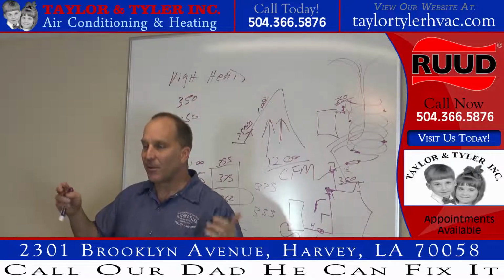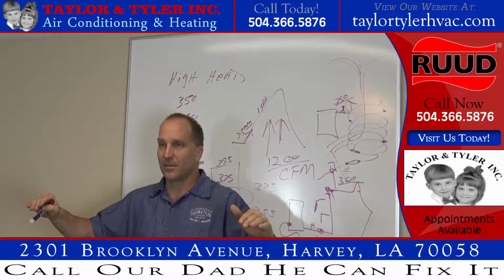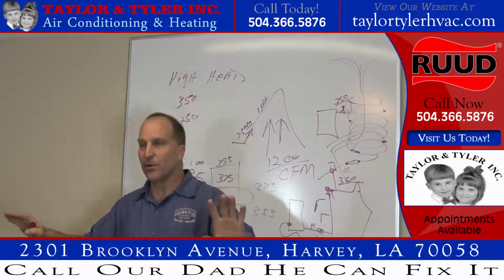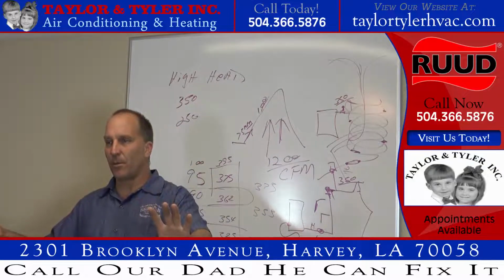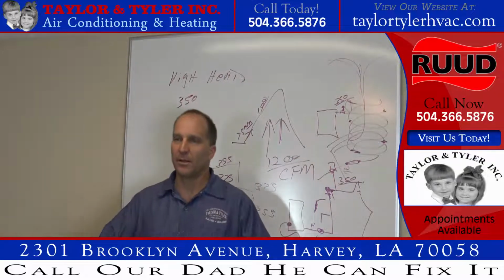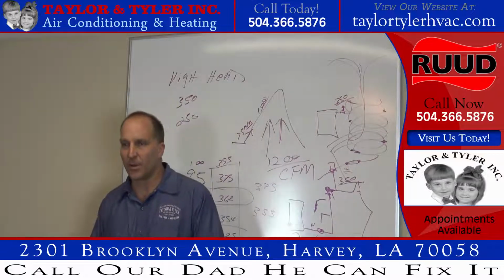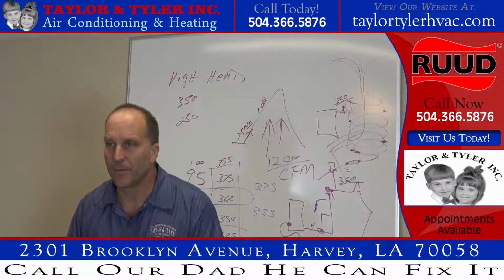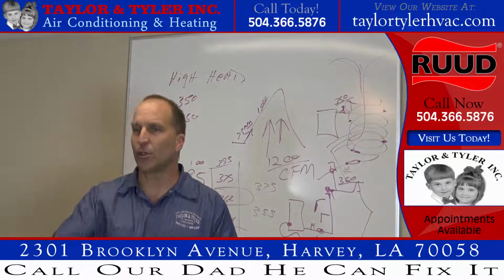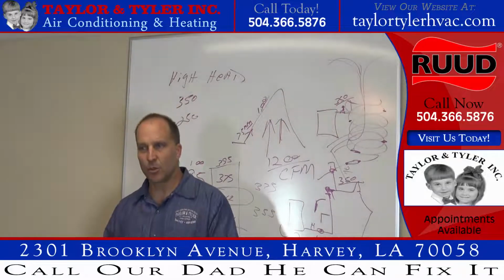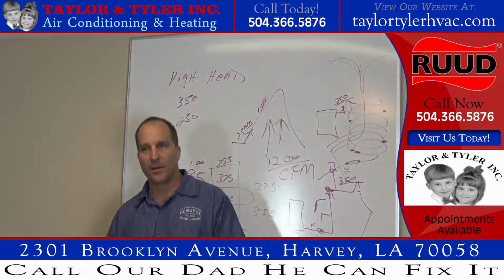Okay. So you have to be able to decipher these things. So you have to first determine, is it a TXV system or a piston? It's a TXV. I know that. I see the valve on the outside of the system. Okay. What's my subcooling? 22, right? What should be my subcooling in this case? 12. We already determined that, right?